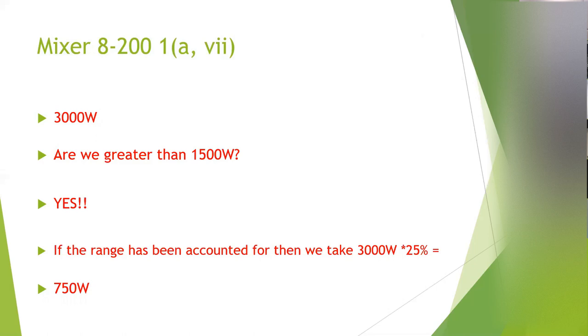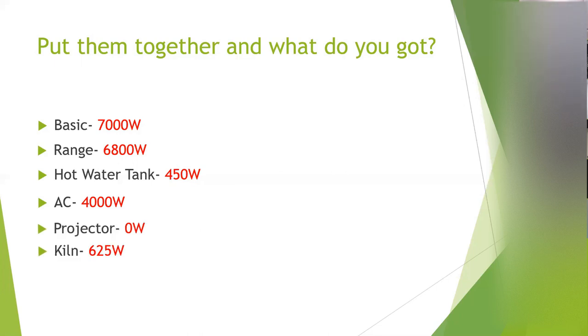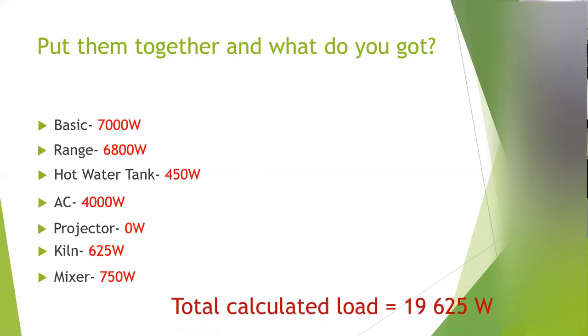Now we add all the loads together: basic load 7,000 W, range 6,800 W, hot water tank 450 W, air conditioner 4,000 W, projector 0 W, kiln 625 W, mixer 750 W. Adding all those together gives us a total calculated load of 19,625 watts.